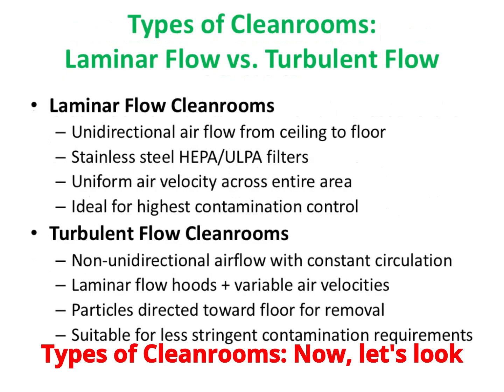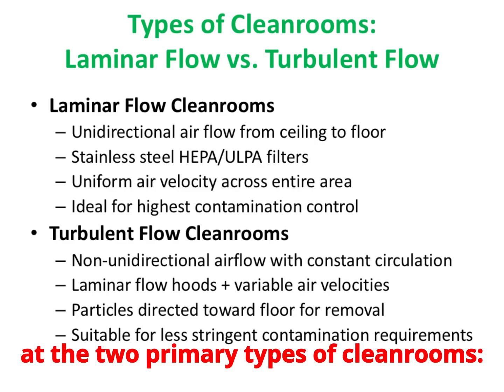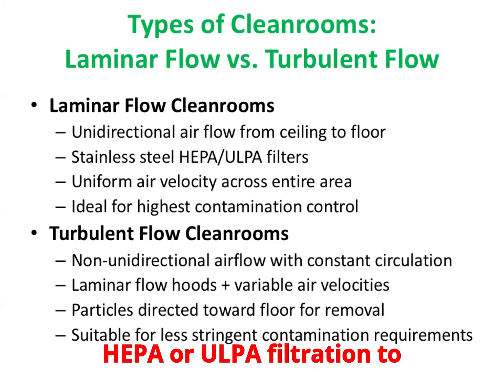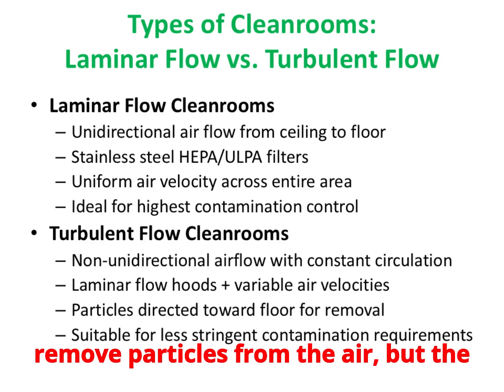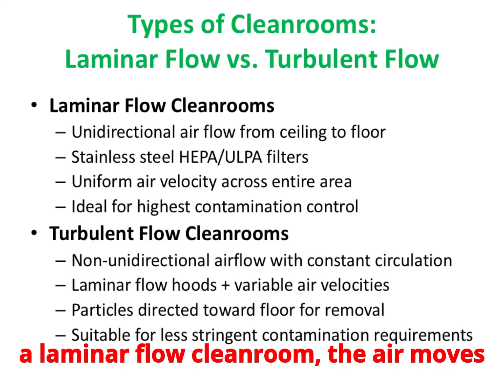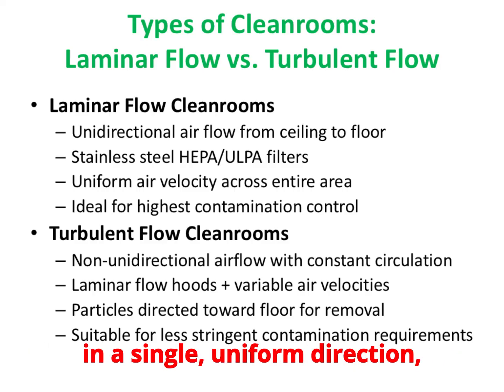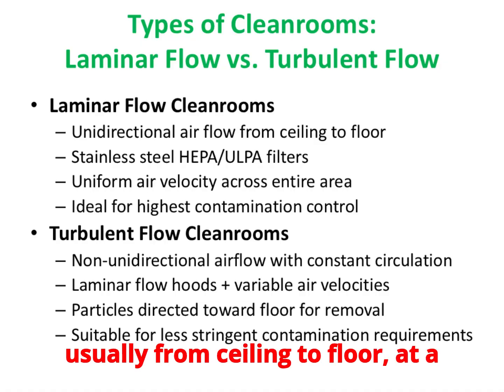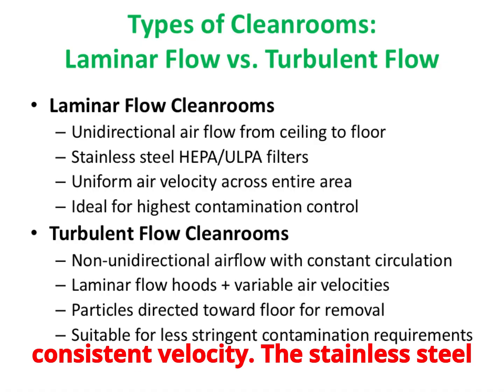There are two primary types of clean rooms: laminar flow and turbulent flow. Both use HEPA or ULPA filtration to remove particles from the air, but the airflow patterns differ significantly. In a laminar flow clean room, the air moves in a single, uniform direction — usually from ceiling to floor — at a consistent velocity. The stainless steel filters ensure minimal turbulence, which means fewer opportunities for particles to swirl back into the work zone.